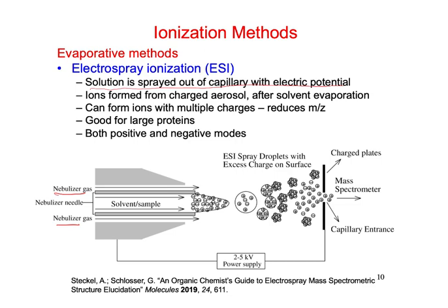So it comes out of the tube with this ionization and with this gas sprayed out. It starts out by making these bubbles or groupings of ions, and then they gradually get evaporated. The solvent gets removed till we get all the way down to where we have these ions over here. So the ions are formed as a charged aerosol, and then the solvent is evaporated.